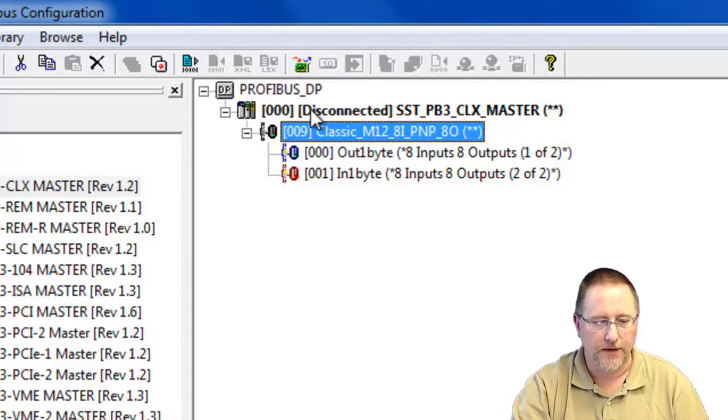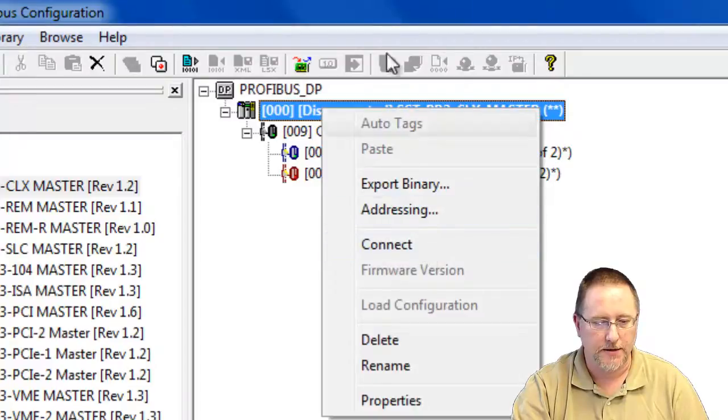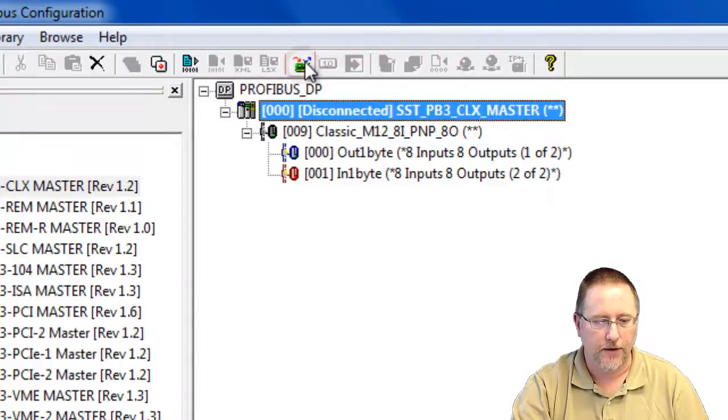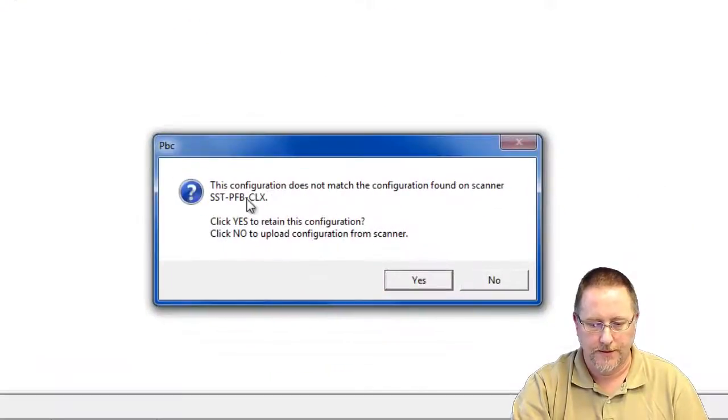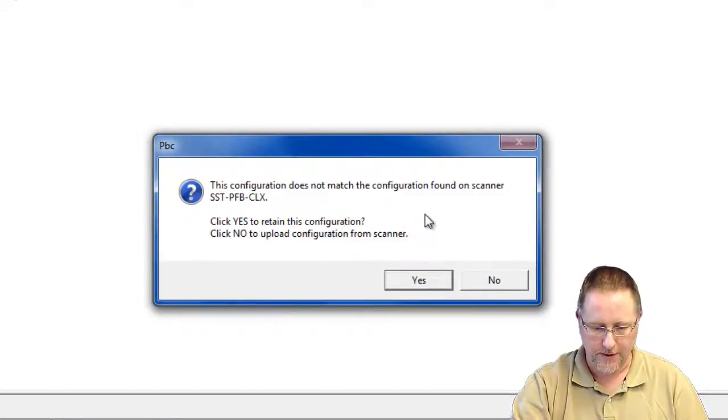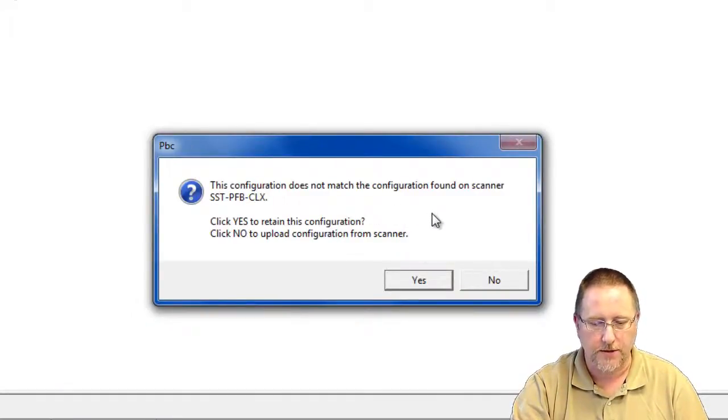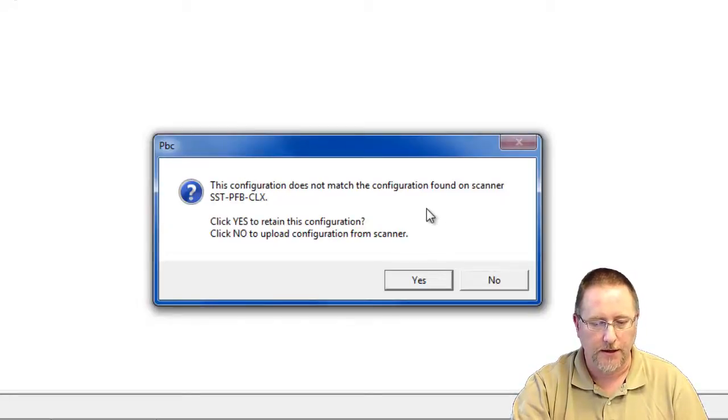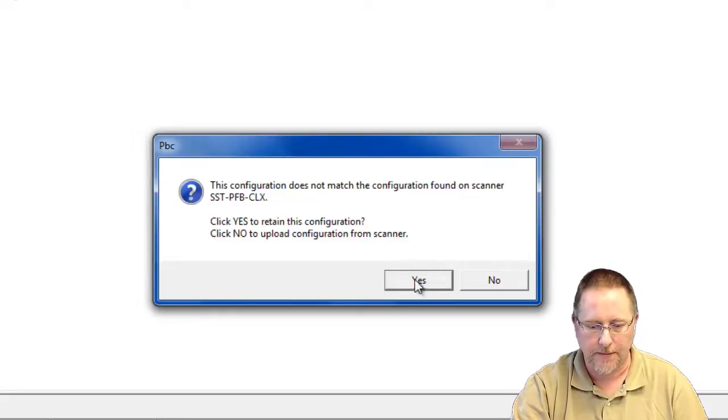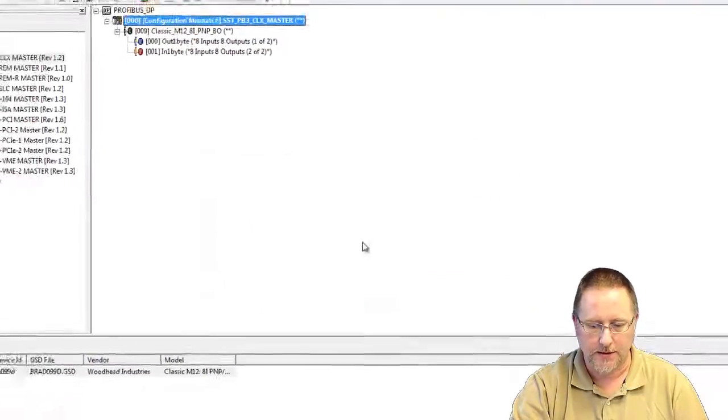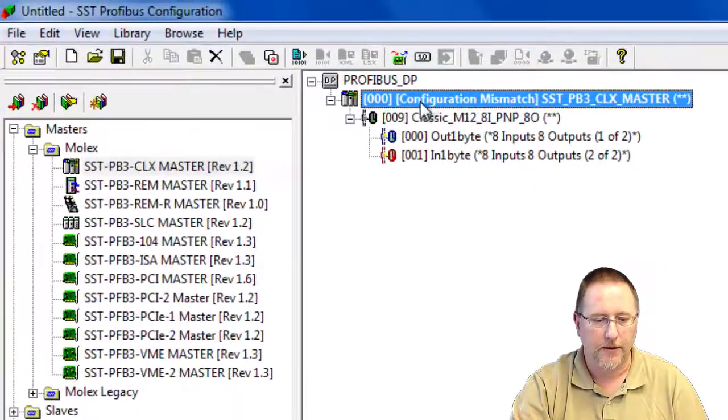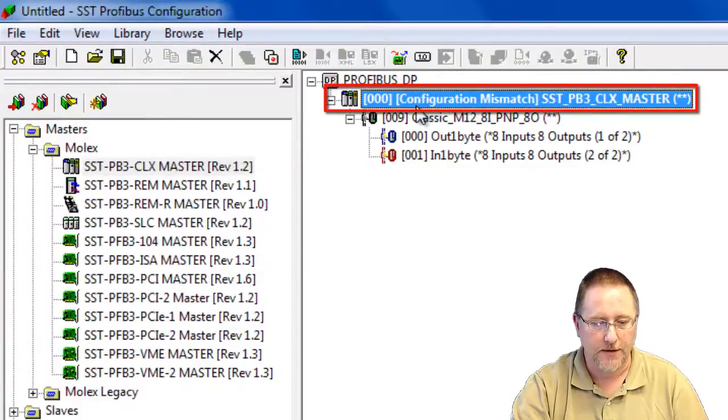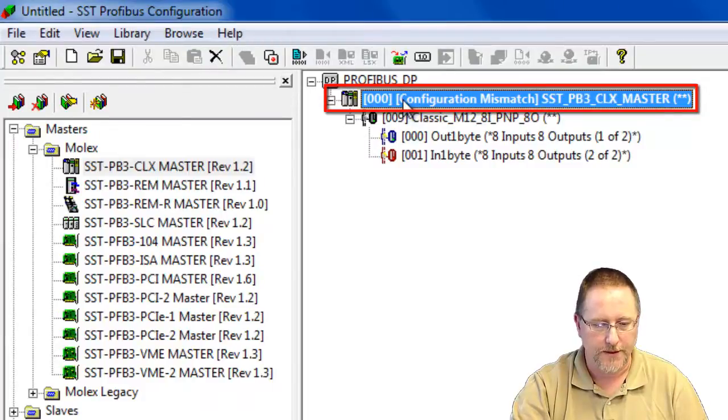Now we need to connect to the module. We select and connect, going up and clicking on the icon. So the message that pops up tells us that the configuration doesn't match. Do we want to retain the configuration in the configuration tool or do we want to upload it from the scanner? Well we want to retain this one because we're going to download it to the module. And now it shows configuration mismatch indicating that the configuration in our software doesn't match what's on the module.